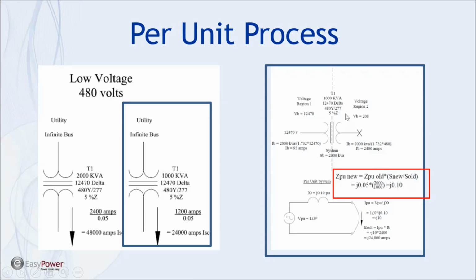So for the 1,000 kVA transformer, the new base VA is 2,000 kVA divided by 1,000, which is a multiplier of 2. So in this system, if I had it in a system with a 2,000 kVA base, the impedance of that transformer would look twice as much as if it was just on its own base, which is what's reported on the nameplate of the transformer. So now we do these calculations, but because I chose S base of 2,000 kVA, when I calculate my base current in this region, I've got to use S base for my system. In the per unit world, my S base stays the same. It doesn't matter what voltage region I go to. You'll see as I add a second transformer here.